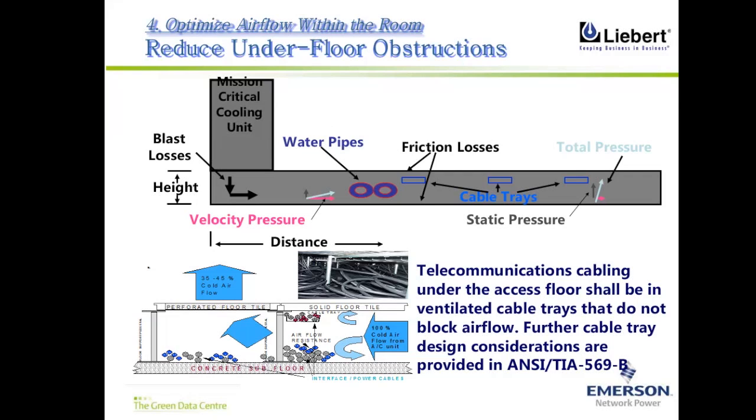So basically, we have to reduce underfloor obstruction. Planning should be very good. We have to plan for the next 4-5 years what all systems will go below the floor, and accordingly we have to make the floor of the data center. To start with, I recommend 450 mm as the minimum for a typical load of 30 to 40 kW. With higher loads, we go for 500 mm or even 1 meter. It all depends on the load.